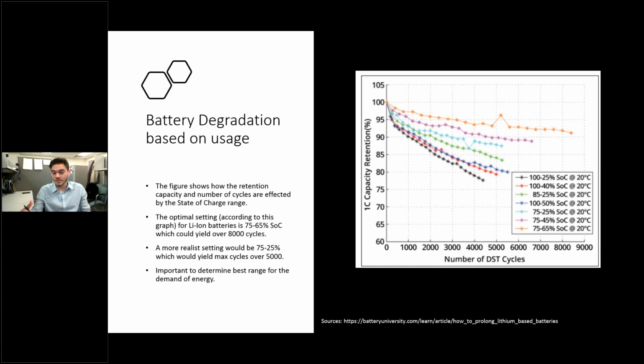A more realistic setting would be between 75 and 25%. The downside is you get fewer cycles, but you're still achieving over 5,000 cycles, which at 365 cycles a year gives you about 13 to 15 years of life before dropping below 80%.